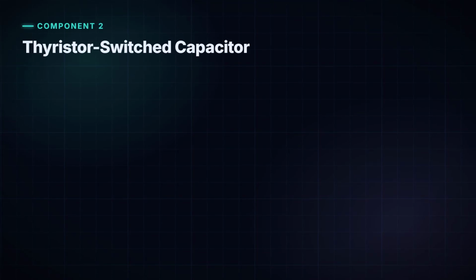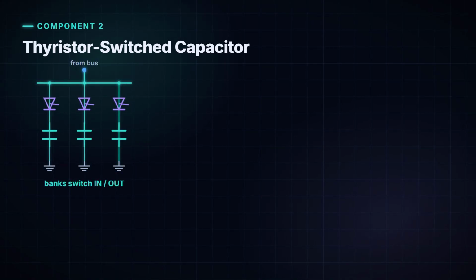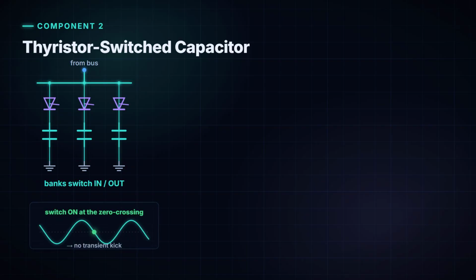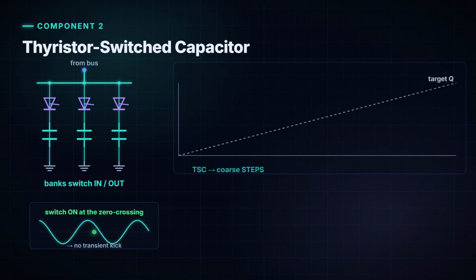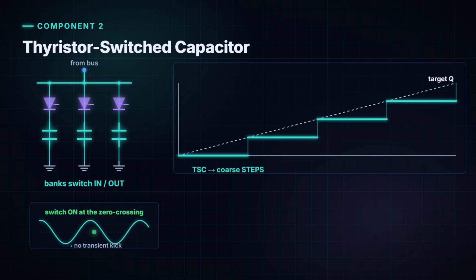The TCR can only absorb reactive power, but often the grid is sagging and we need to supply it. That's the job of the thyristor switched capacitor, the TSC. It's a bank of capacitors and thyristors that switch the whole bank in or out. But notice the difference in how we use the switch. With the reactor, we varied the firing angle for smooth control. With a capacitor, we can't do that. Chopping a capacitor's current would cause a violent current spike. So instead, we switch the whole bank either fully on or fully off, and we do it at the exact instant the voltage across the capacitor matches the grid, the zero crossing point. So the transition is completely smooth, with no transient kick. The trade-off is that a TSC gives us reactive power in steps, not a continuous range.